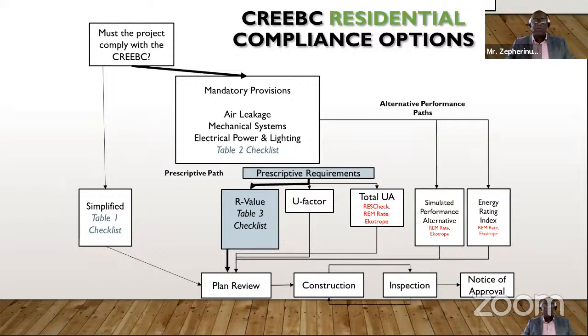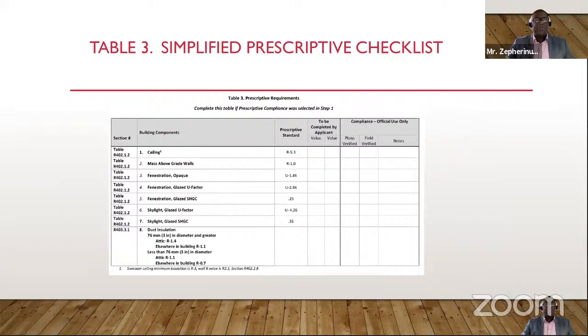The simplified one is what is referred to as the R value, and there is a Table 3 checklist to explain that. So this Table 3 is the simplified prescriptive checklist. If you are demonstrating that your project is in compliance with the code, then you would follow through the various requirements for your ceiling, your mass above grade walls, fenestration, skylights, the duct insulation, duct testing, and include this information as far as what the code requires and what you are recommending or have included in your design.